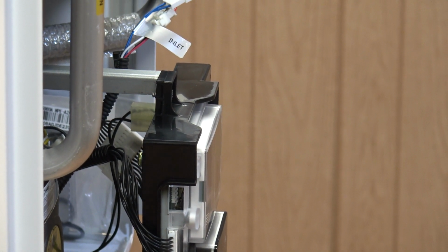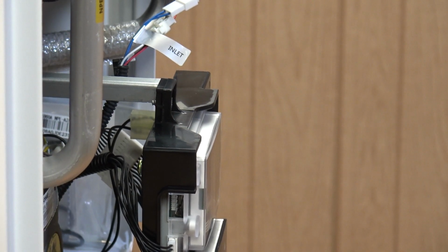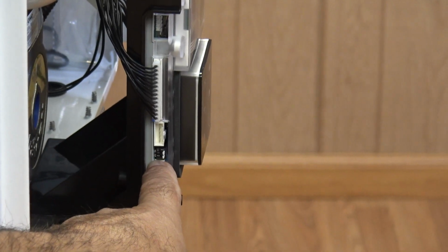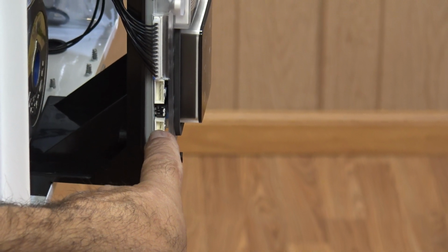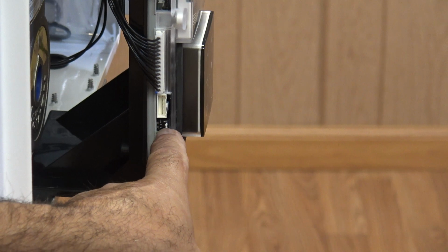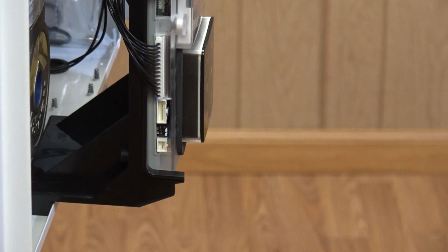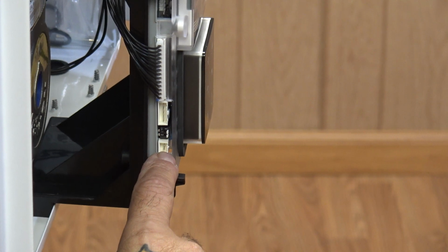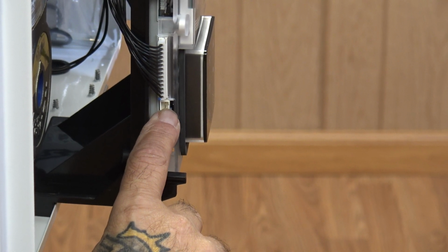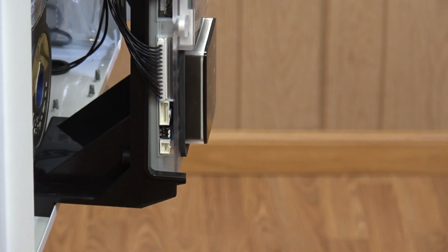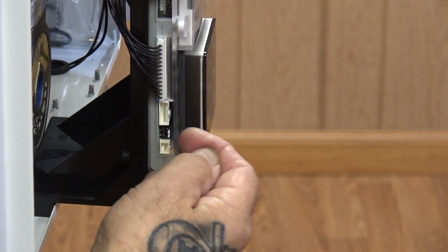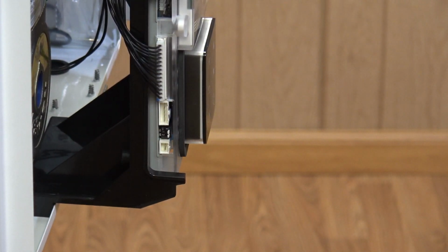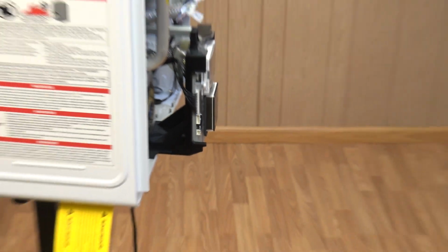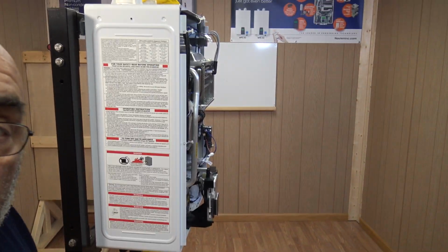Let me get this right where you need it. Right here. I'm gonna go down a little more. Sorry. Okay. Right here. There's 2 tiny dip switches. There's 1 and 2. So between the external controller and the communications cable, there's 2 dip switches. Dip switch number 1, which is the top one, has to be pushed to on, this way towards the actual interior of the unit. What that does is now tell the PC board it's propane gas.